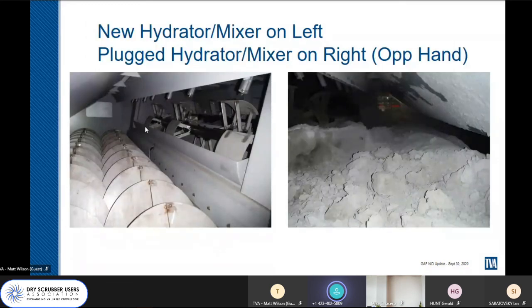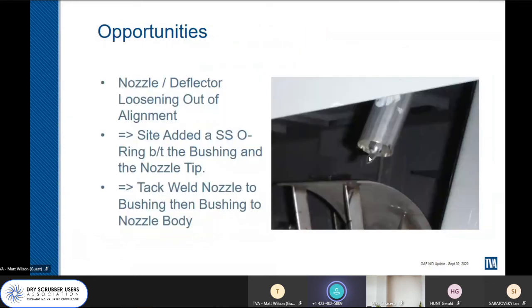That mixer hydrator, brand new one, is on the left. This is the internals of Alstom's hydrator design. This is considered the mixer area of this hydrator mixer. This is what it's not supposed to look like when it's plugged. So there are opportunities that Gallatin learned on the nozzles, and basically this is a close-up view of the nozzle. It has a shield, this is the nozzle tip, and they ended up putting a stainless steel O-ring between the bushing and the nozzle tip, and then tack welding everything to keep the nozzle from rotating out of position.